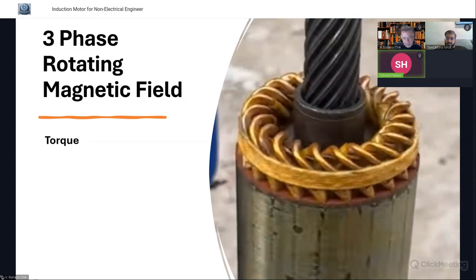The stator core is actually metal. Sorry, rotor. Oh, you want the rotor. Yeah, is the rotor a winding as well, or a permanent magnet? No, the rotor is winding as well, because if you see this, this is a rotor bar. So the number of slots and everything is also similar, reflecting the stator side? Is it duplicating the stator side? Yes, definitely, because on the other side it has 24 slots. That means on this side also 24 slots, I see. Because it has to be aligned with the stator magnetic field. Understand. Okay.